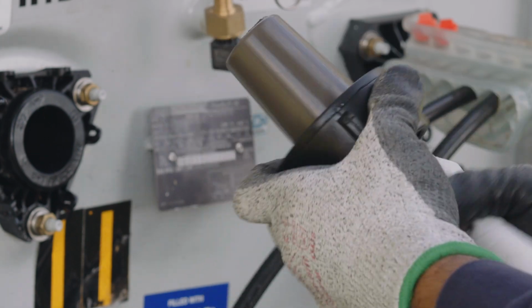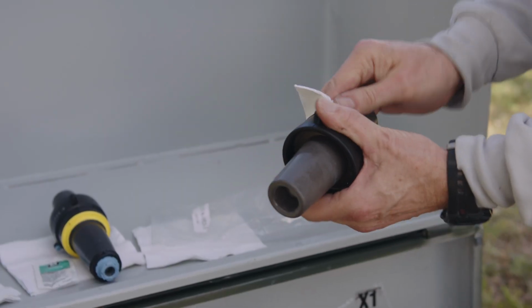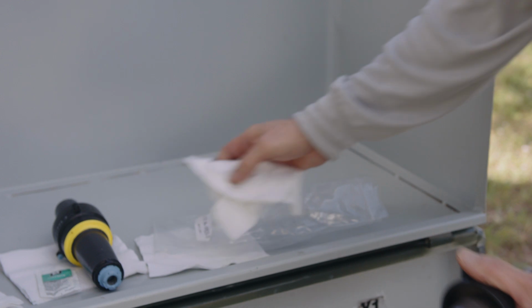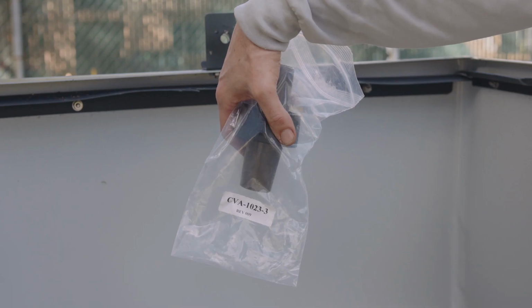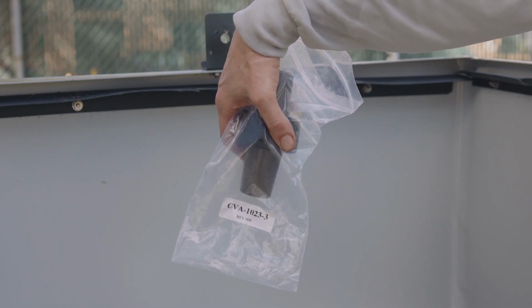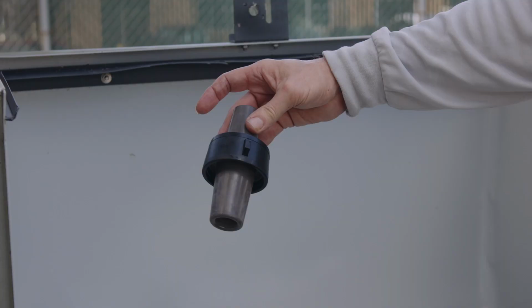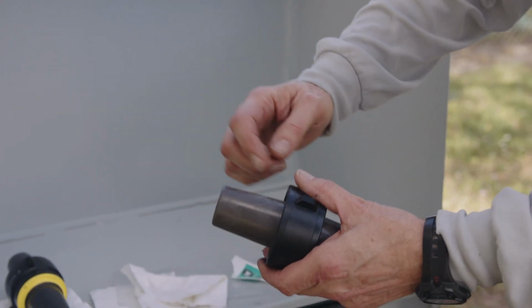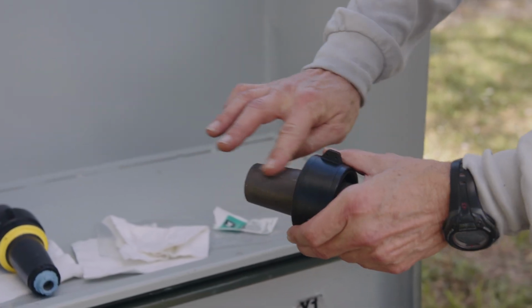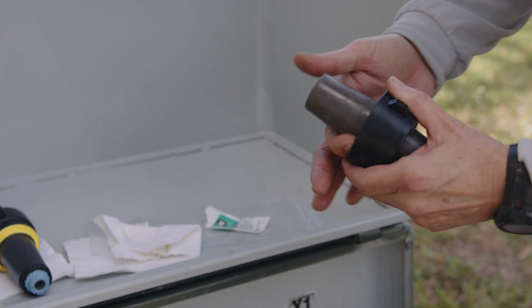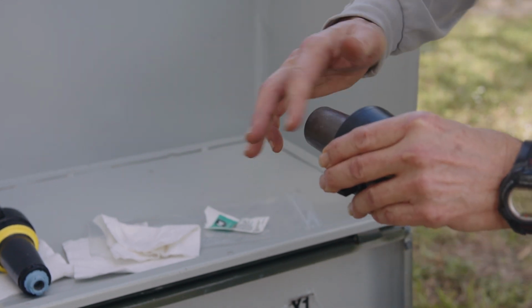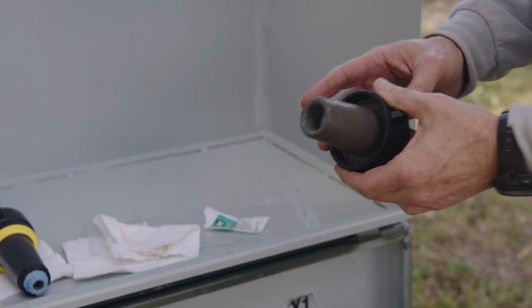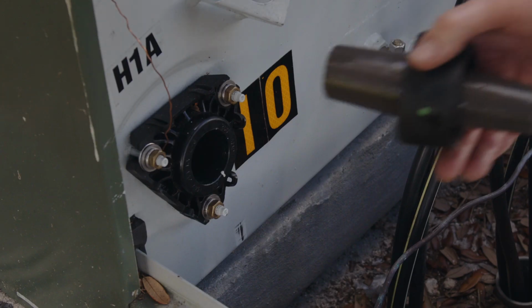Step 3. Remove the shipping caps and clean the bushing well adapters for the H1A and H1B bushings with a soft cloth. The bushing well adapters are included in the installation kit. They look like load break inserts but are shorter and gray. Step 4. Grease the bushing well adapters on the taper to be inserted with silicone lubricant included in the installation kit. The larger taper is inserted into the bushing well.